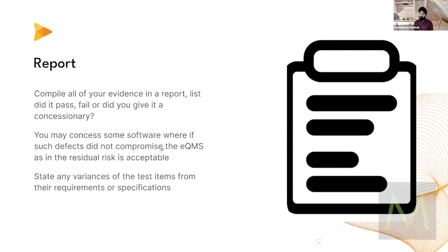Compile all the evidence into a report. The evidence doesn't have to be in a single report — SaMD companies often use Jira tickets for each particular software and put evidence there, then the report has the Jira reference numbers. Where you store it is not too critical. For companies using Jira, manually download your XML file every week or so — because if the Atlassian systems go down, you still have the XML file with all your data.